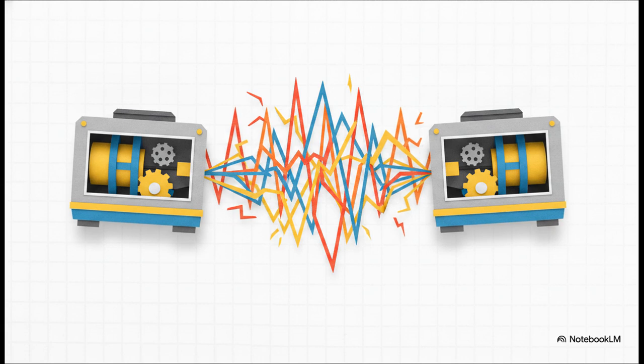Excessive sensitivity in the governor, insufficient mechanical damping to stop the oscillations, and rapid, frequent load variations. Now, if you just have a single generator supplying, say, one single factory, hunting is annoying. But what happens if you connect multiple, perfect isochronous generators together in parallel on a shared electrical grid? Oh man, they fight each other.